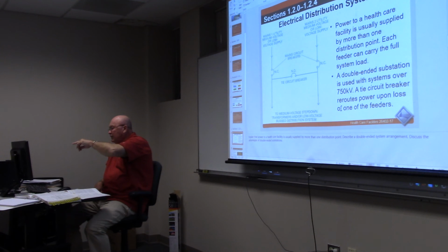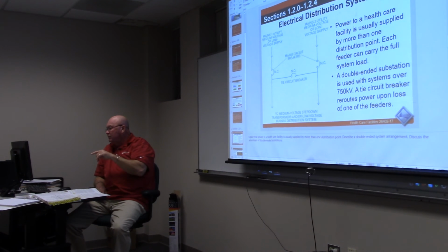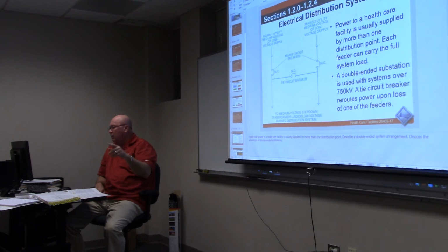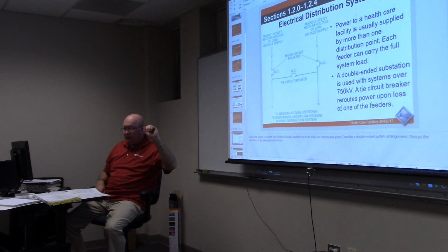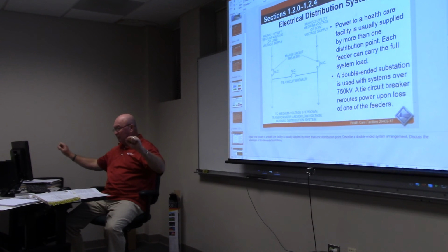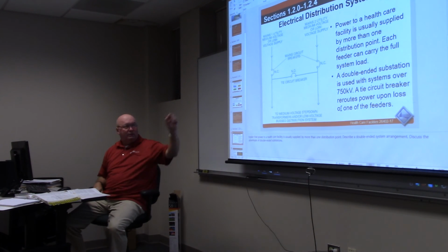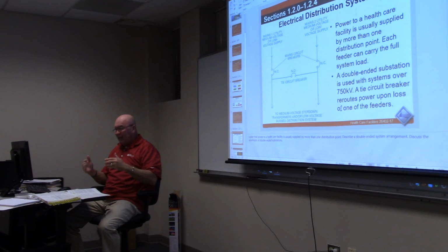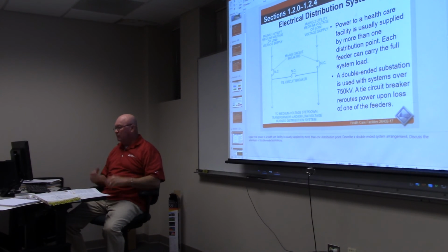Power to a healthcare facility is supplied by one or more distribution points, and each feeder could carry the full load of the system. That's important; we couldn't put a 2,000 amp and a 1,000 amp together. If it's 2,000 amp, both have to be capable of carrying that whole load, the entire load.